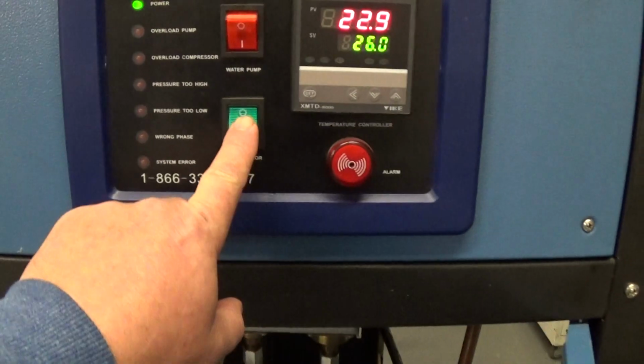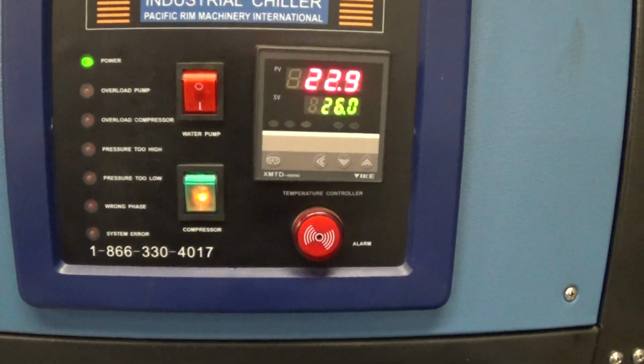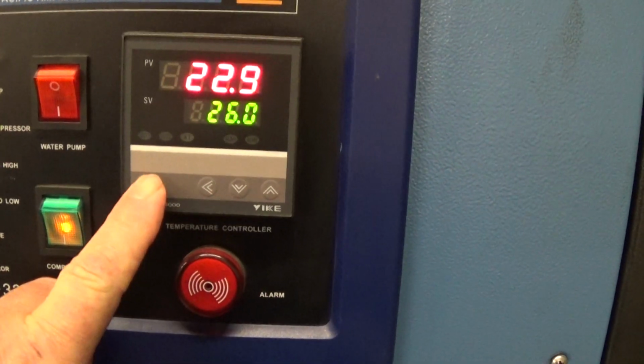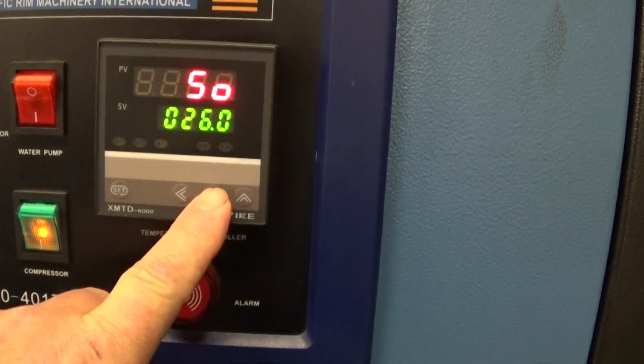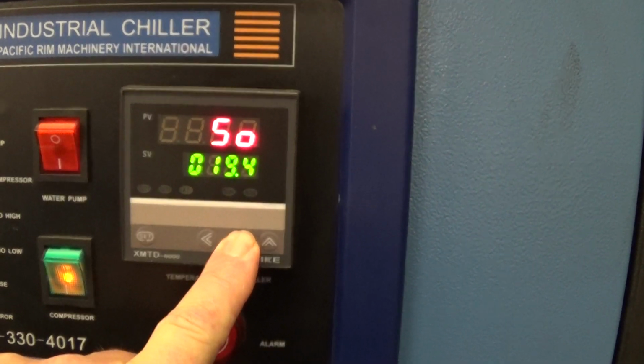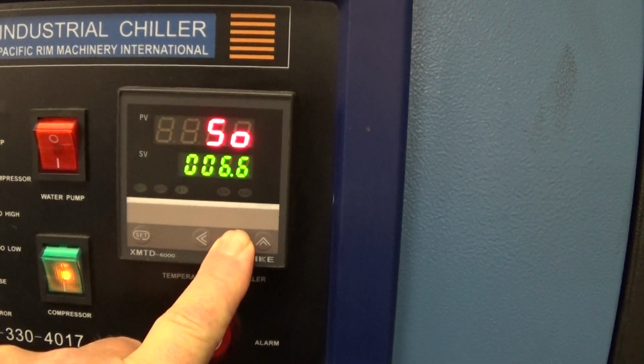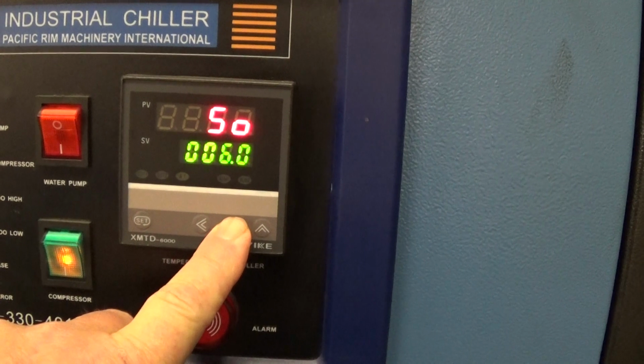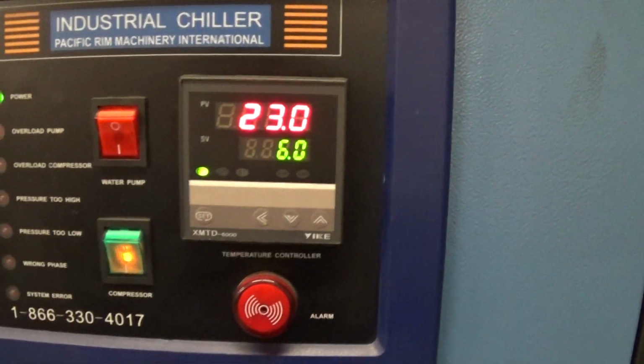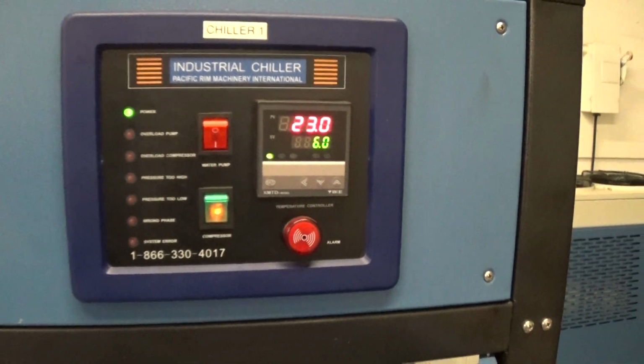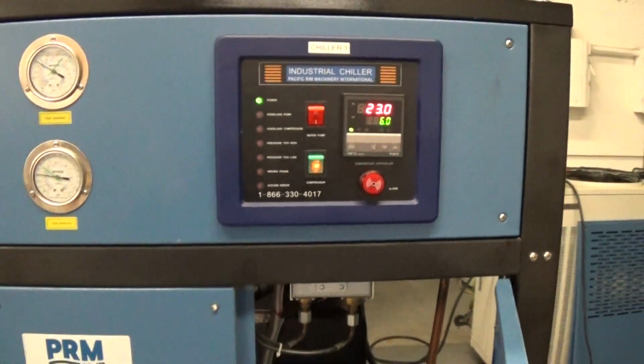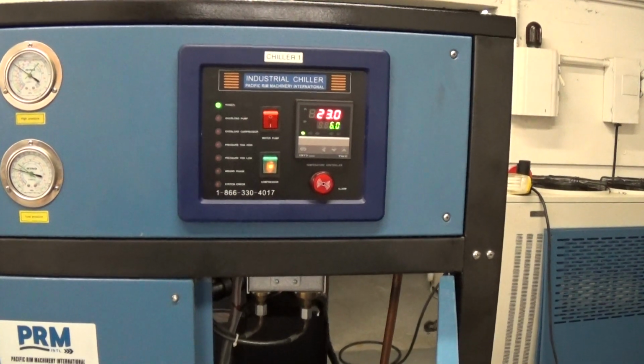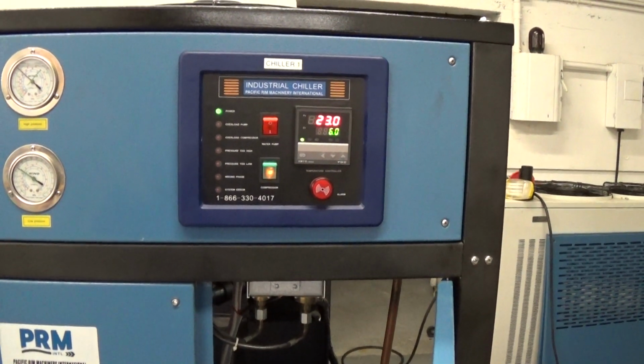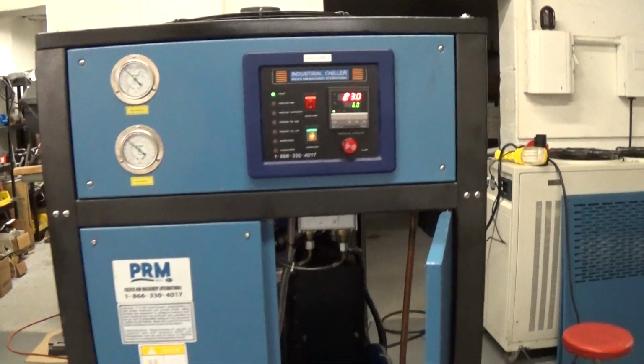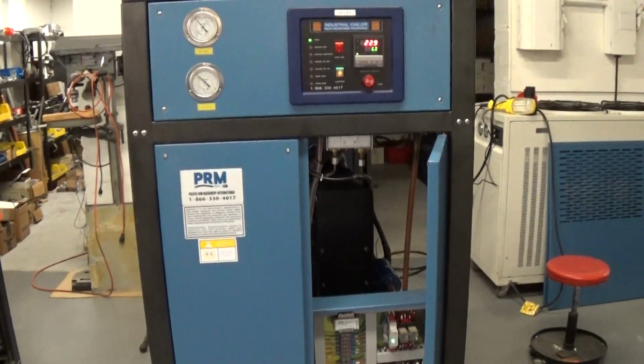We're going to go ahead and turn the compressor power light on. To change the set point, it's very easy. We press set, then you see the lower set point number flashing. Just going to bring it down, and today we're going to run it to, let's say, 6C. Okay, going to press set again. Start chilling. In this case, because we had the power on and the pump running, there was no delay. On a fresh startup, there will be a 3-minute delay for the compressor to start to let things stabilize.